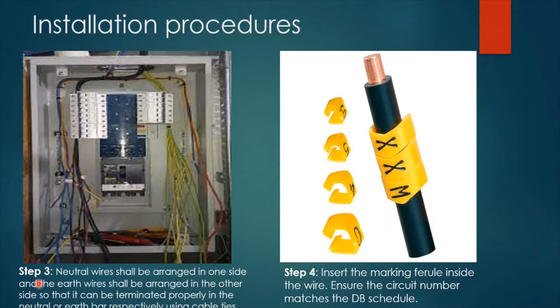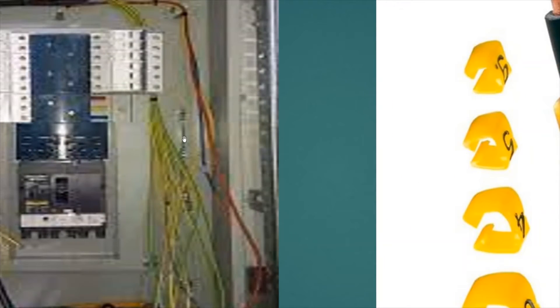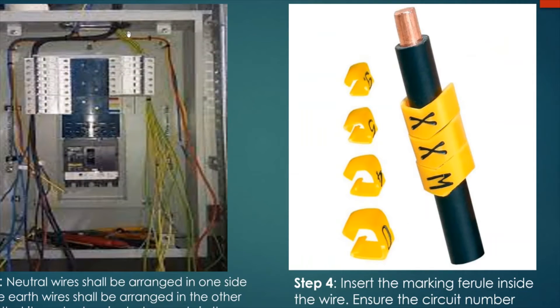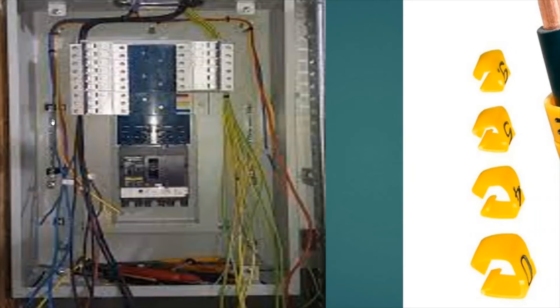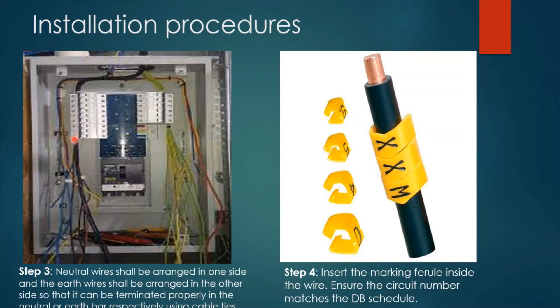Step three is to arrange the neutral wires and the earth wires on both sides of the distribution board according to their terminals. For example, the earthing wires are brought to the earthing terminal side, and the neutral wires are brought to the neutral bus bar on the other side. Step four is to insert the marking ferrule inside the wire, ensuring the circuit number matches the exact number mentioned in the DB schedule. For example, if the wire is protecting circuit number R1, you select a ferrule with the letter R and the number 1.